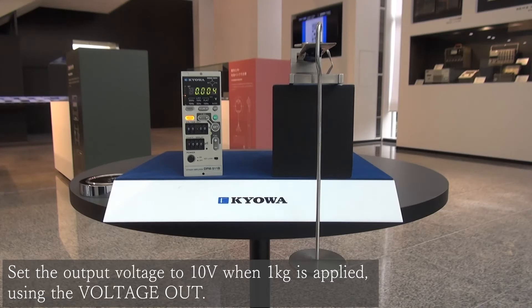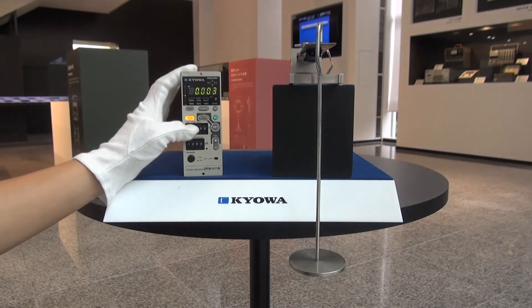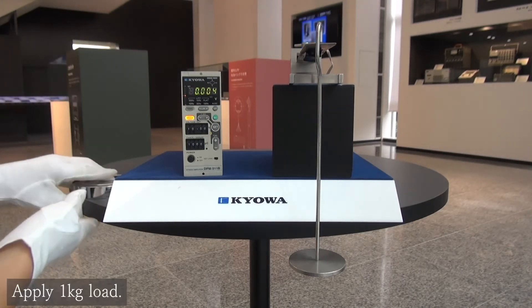Then, use the VOLTAGE OUT switch. You can set the output voltage to 10 volts when 1 kg is applied. After this, actually apply a load of 1 kg.